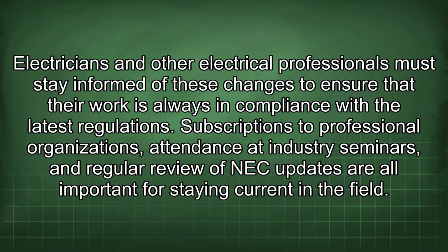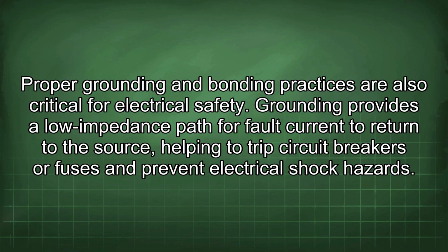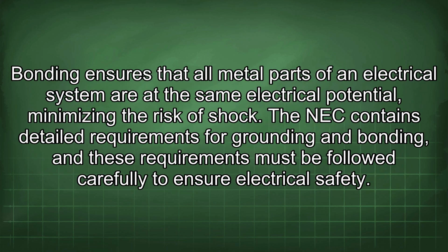Proper grounding and bonding practices are also critical for electrical safety. Grounding provides a low impedance path for fault current to return to the source, helping to trip circuit breakers or fuses and prevent electrical shock hazards. Bonding ensures that all metal parts of an electrical system are at the same electrical potential, minimizing the risk of shock. The NEC contains detailed requirements for grounding and bonding, and these requirements must be followed carefully to ensure electrical safety.